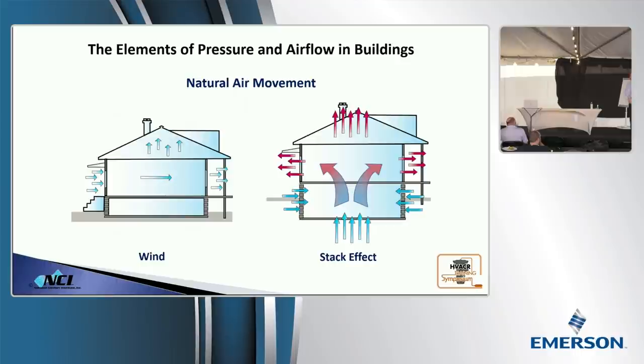A lot of guys say, well, I've got a cold flue. If you have a cold flue, you're fighting a building problem. Air comes down through depressurization. This is where we start to talk about some of these influences. These are just natural influences. You can't control air in a leaky building.